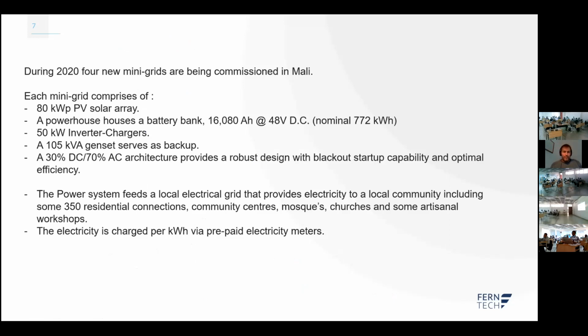This mini grid, and I think it's the same for all 4 mini grids in Mali, is an 80 kilowatt peak PV solar array. You'll now see a few pictures. For this mini grid, a powerhouse was built to house the inverters, power electronics, and the battery, which works at 48 volts DC with a nominal capacity of 700 kilowatt hours.